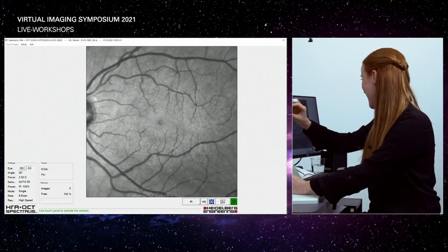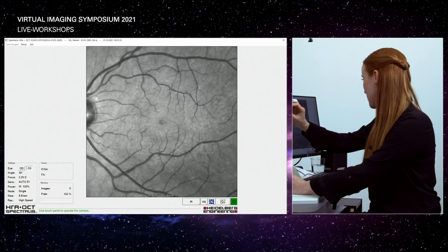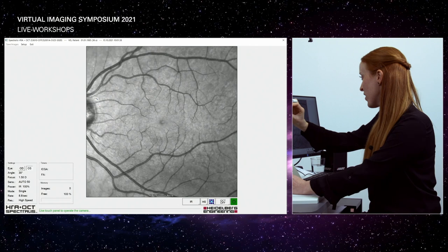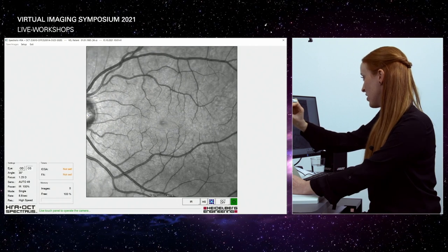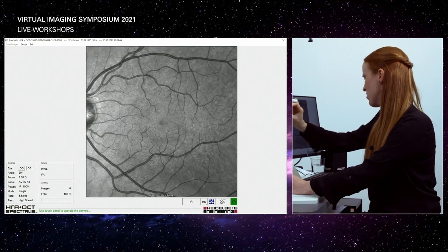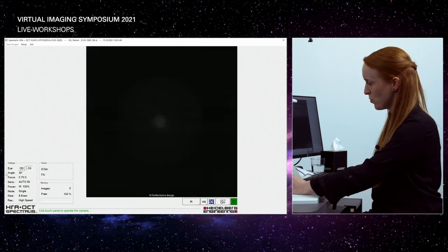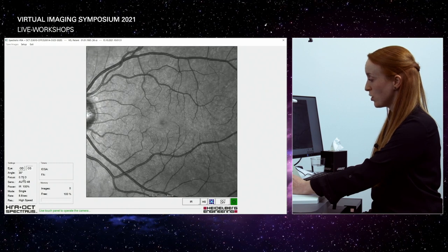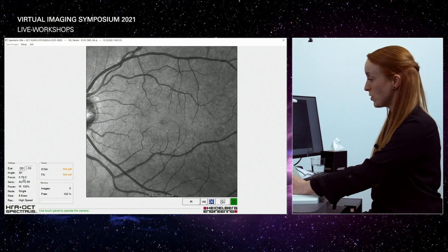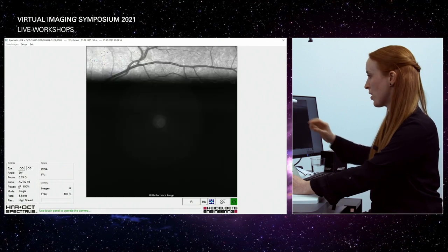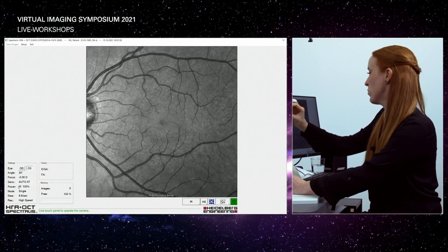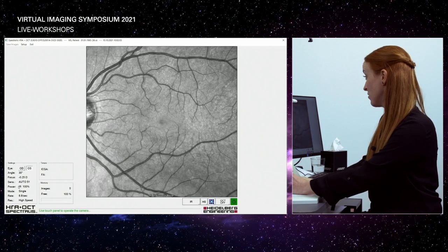Okay, good. And as I said before, when we have found the perfect focus for our patient in infrared, from that value that you can find in the lower left of your acquisition window, you just do a defocus of minus one diopter.